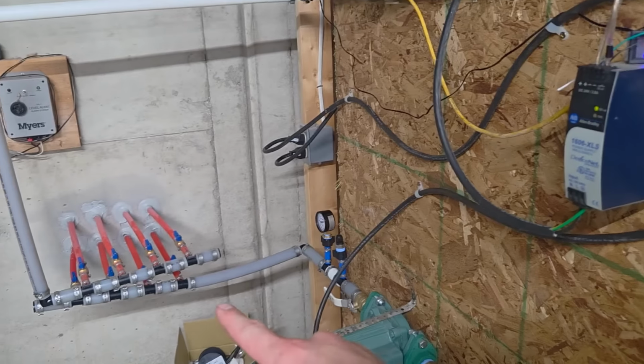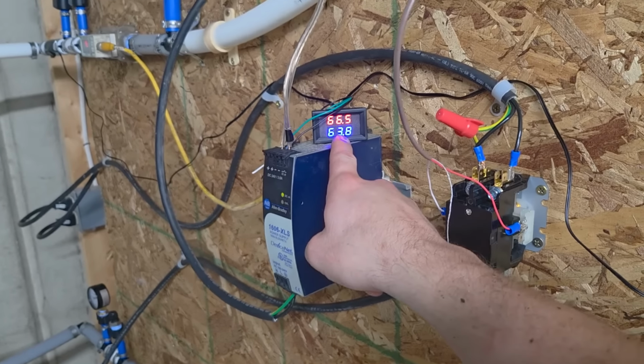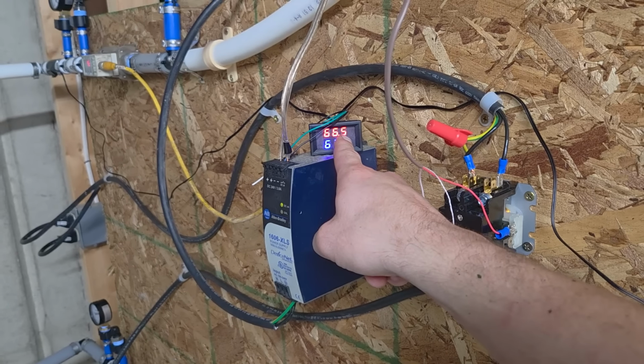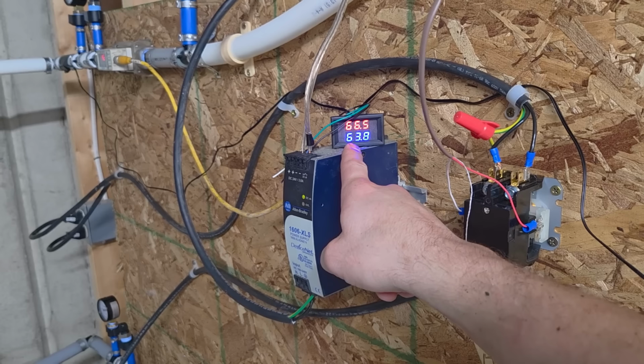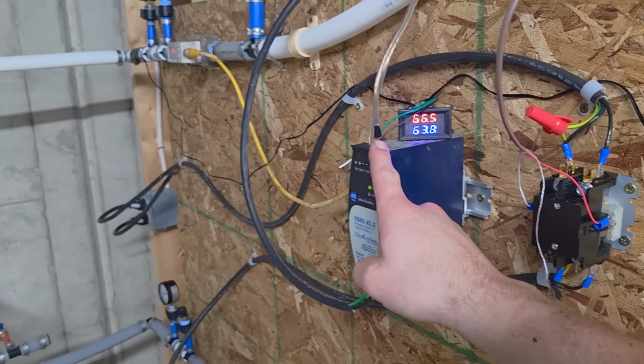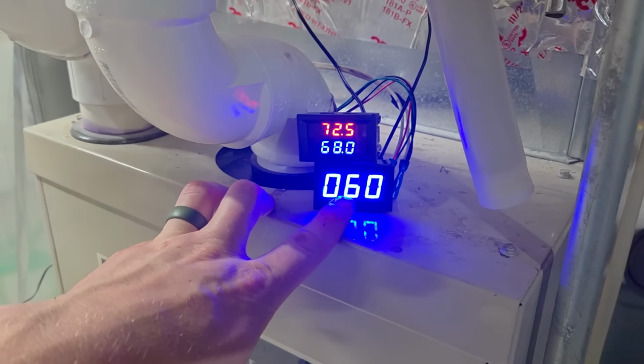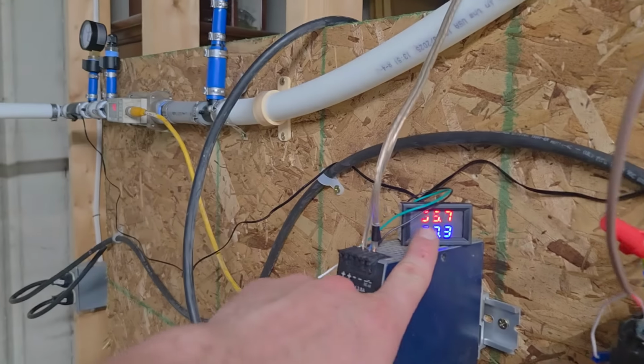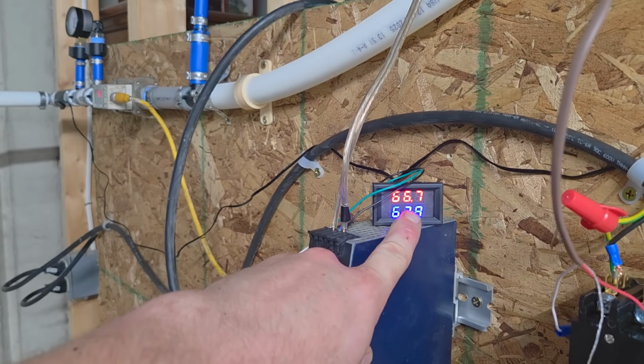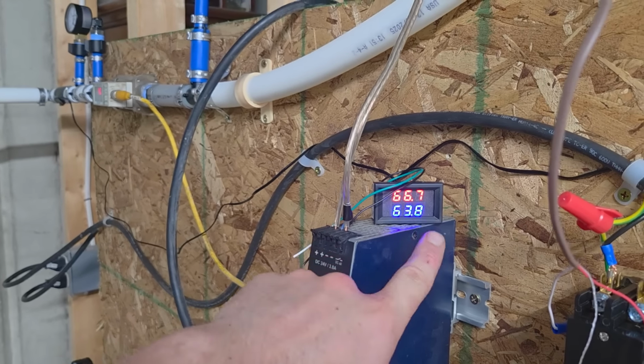Day 264. Just kidding. 1 hour in. My water coming out of the well and into the ground loops is 63.8. And my water coming out of the ground loops is 66.5. So my ground loops are warming up the water 3 degrees. The water at the heat exchanger is 60 degrees. You might be wondering, how are you at 66 degrees, almost 67 degrees, coming out of the ground? And then when you're in the heat exchanger, you're at 60 degrees. How are you cooling off?